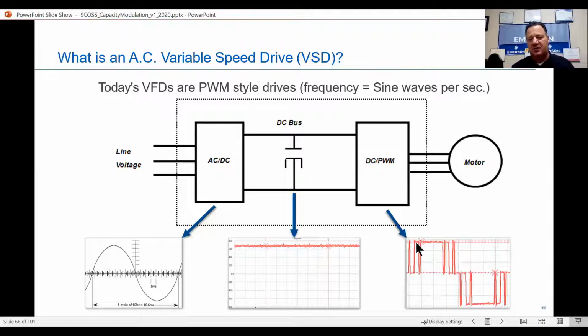Not that you need to know this when you're out in the field, but when you're teaching it, you want to just know the longer these lines are here, that's the longer it's staying on, okay? If they're shorter in sequence, they're coming on and off, and that sine wave will be tighter, okay? It won't be near as high and low as this is. So the more often you're making those switches, we're getting less hertz. That line's going to be closer to the center line, if you will.